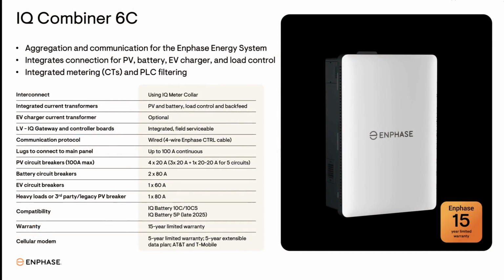The Combiner 6C has several important features. The ability to operate in grid-tied system configuration and integrate and interconnect with a meter collar to provide backup system capability. Bus-integrated CTs to simplify metering installation. A simplified, low-voltage gateway for resilience and reliability. All-wired communications for reliable system performance. 100 amps continuous backfeed for solar and energy storage.